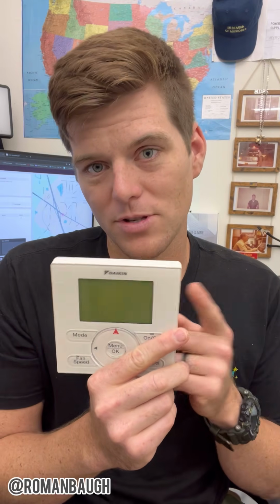Something else that can cause short cycling. You've got supply air dumping right back into the return air on a cassette that's been put up against an actual wall. They make block-off plates for those types of units that will reduce the amount of air that's being recirculated back into the return air thermistor. Something like that kind of application would require you to put this controller a decent bit away and also select the field settings to use this controller over the return air thermistor it sees in that unit. That would extend, right, the actual runtime of that system and allow the system to stabilize.